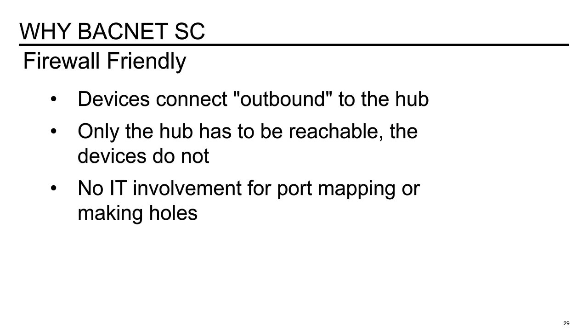And then a firewall is a network security system that monitors and controls incoming and outgoing network traffic based on predetermined security rules. And a firewall typically establishes a barrier between a trusted internal network and an untrusted external network, or the World Wide Web. So making a hole in the firewall allows for inbound traffic from the external network based on predetermined criteria. So the disadvantage with port mapping and managing firewalls is it makes network management more complicated. So with BACnet SC, you eliminate some of those complications.